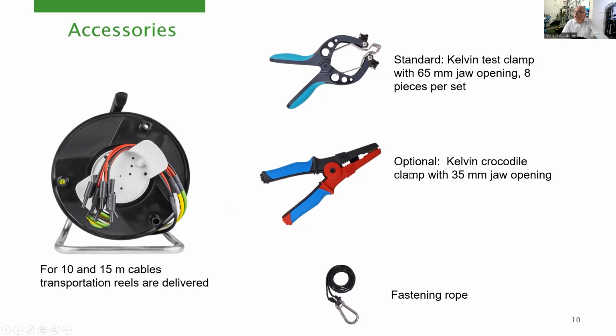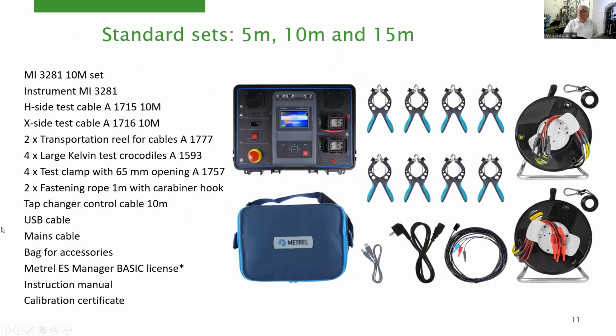Optionally, other clamps can also be used, which are also very well known from DTA, for example. And these long cables are on the reel, which is actually only for transportation of these cables, but makes use of them very simple. Sometimes, if we are connecting to very high transformer terminals, we need some additional fastening of the cables because of their own weight. So one typical set of this instrument: clamps 8 times, cables on the reel, an additional tap changer control cable, power supply, USB, and that's it.